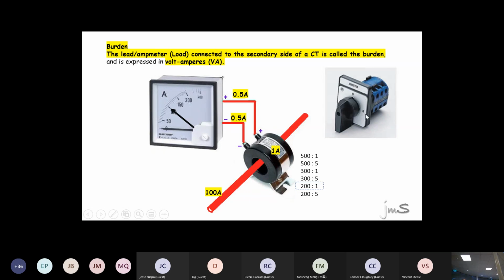Right, on an ammeter selector, you can select red amps, white amps, or blue amps, and off. But I'm going to ask you the question. When the ammeter says off, what happens with those two terminals? What must you do? A, leave them open, or B, short them out? Always short them out. Now guys, when I was an apprentice, I saw it firsthand. A trainee disconnected the two wires here and replaced the ammeter. By the time he connected it up, this thing had already melted.